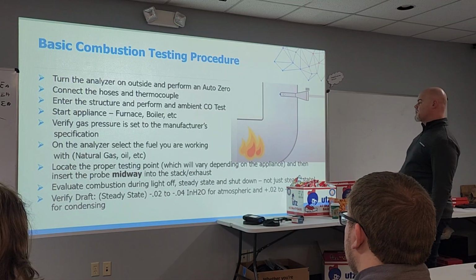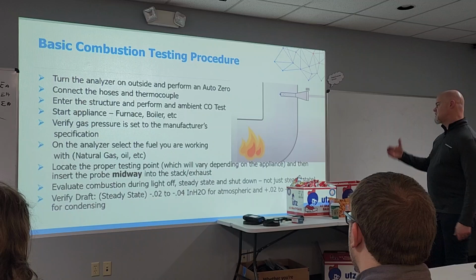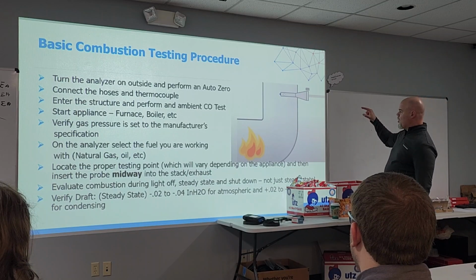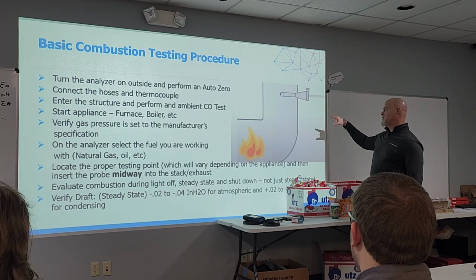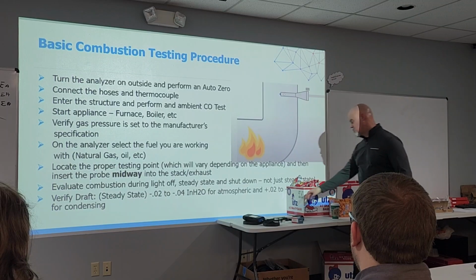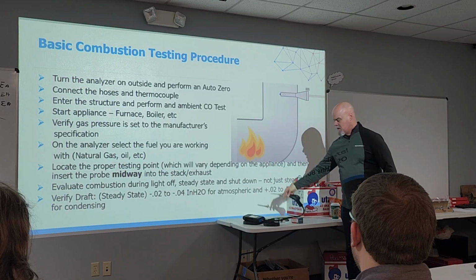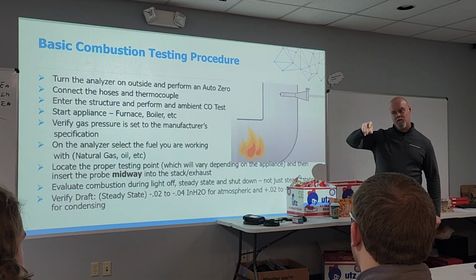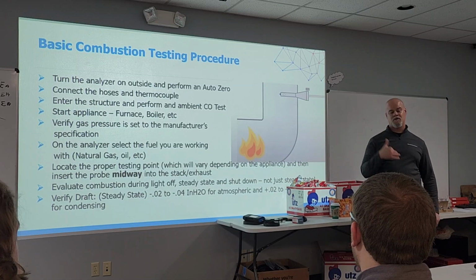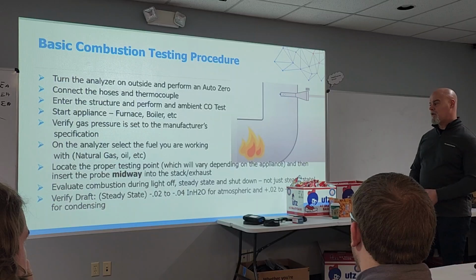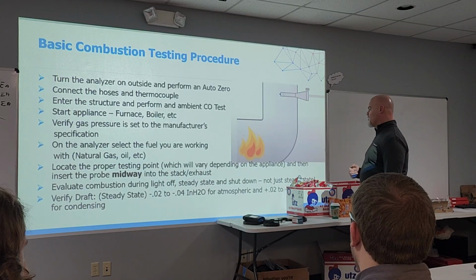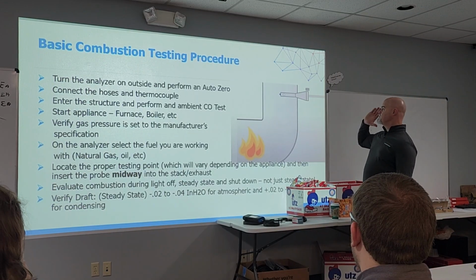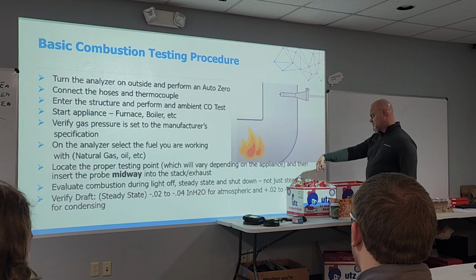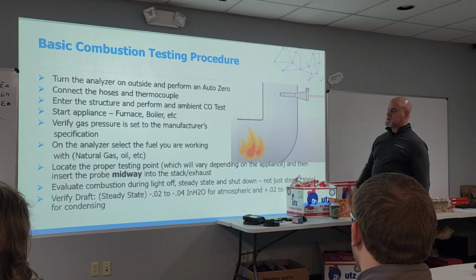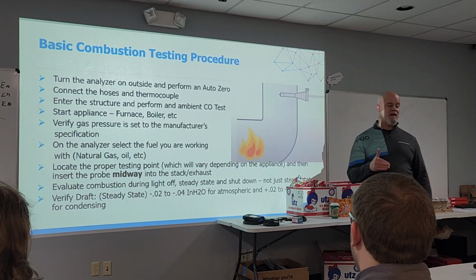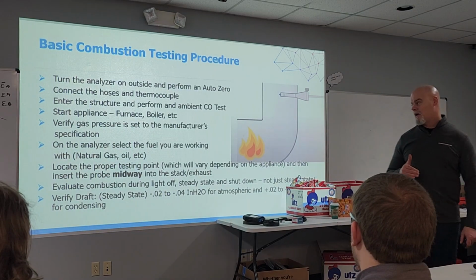Okay? Now locate the proper testing point, anywhere from 6 to 10, 6 to 12 inches above the breech. We put the probe in midway, we lock it down with the positioning cone, because if we don't lock it down with the positioning cone, which is what you see here, this cone is threaded, this gets inserted into the flue pipe, probe gets inserted midway, we lock it down. If we don't use a positioning cone, the probe falls out, we go to catch it, we can get burned. We don't want it to get burned, okay? We're not looking to do a rendition of Grey's Anatomy and go to the hospital or ER, okay? So, probe gets inserted midway, gets locked down with a nut on top of that positioning cone, and you test properly. We don't do anything halfway in this process here. We do everything the correct way, okay?